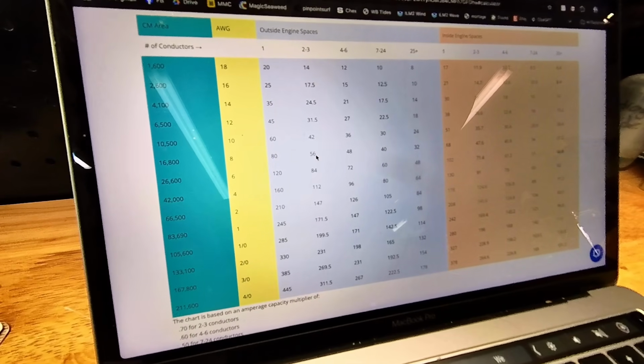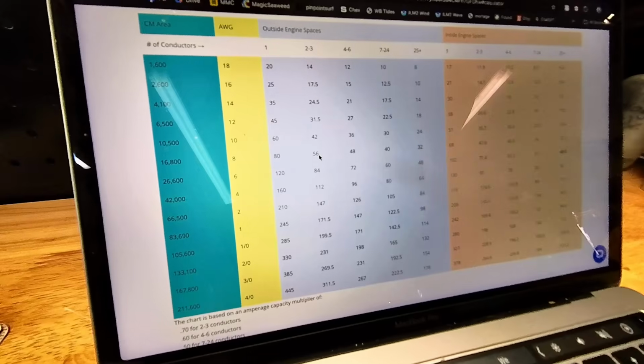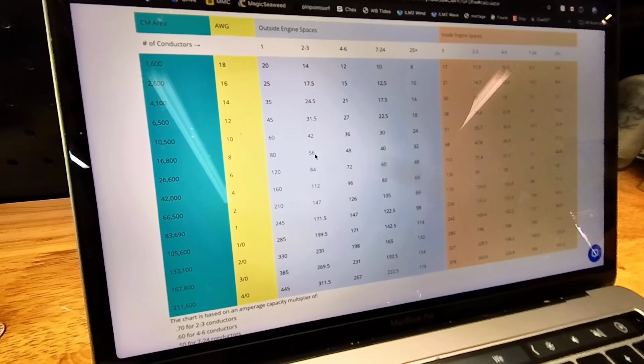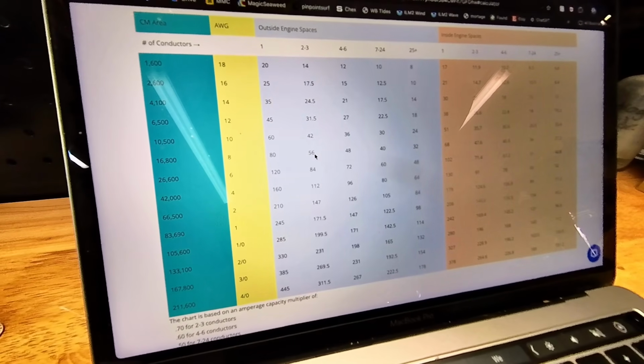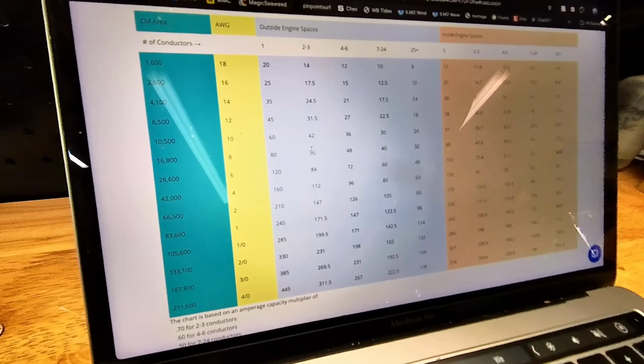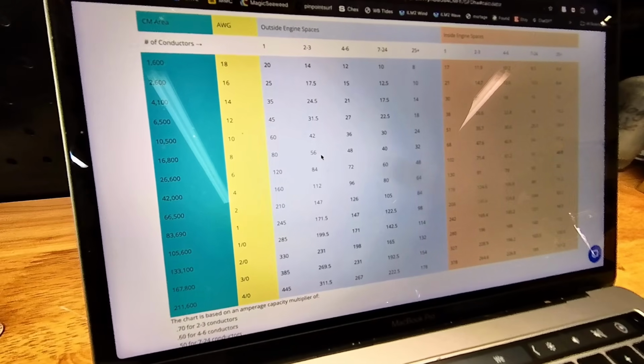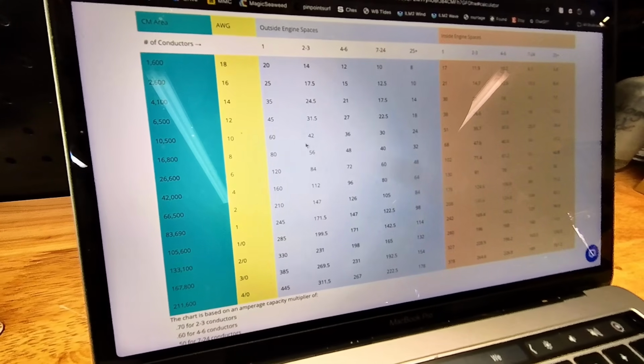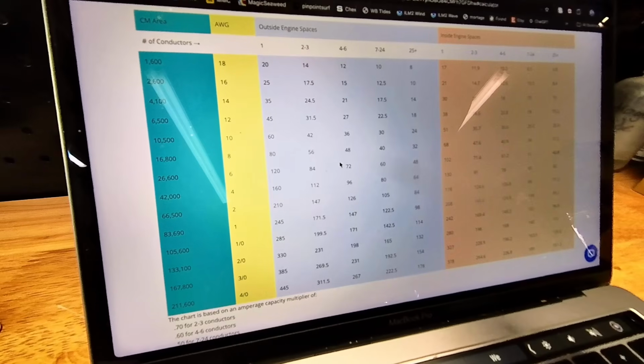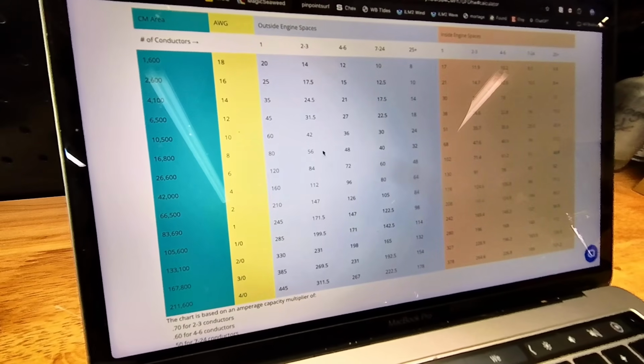So that's a lot. And really what that's going to let us do is, A, we have to make sure that our total load is nowhere near the total ampacity or amp capacity of that 8 gauge wire. We said it was 23 amps, so we're like half of that. That's great. Being conservative is good, remember. We have a safety factor of about 2.